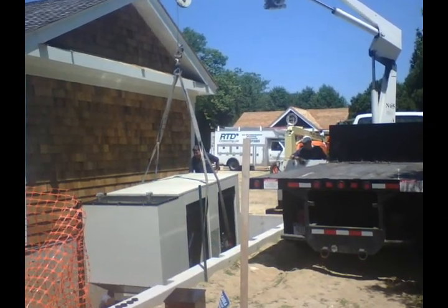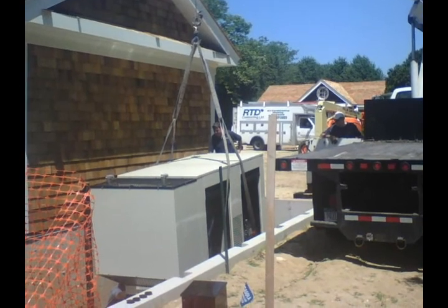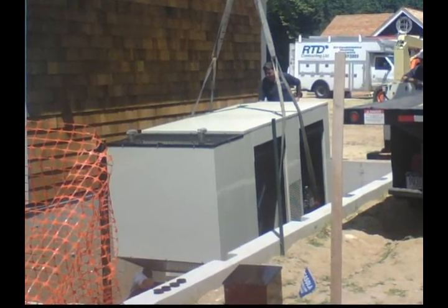Okay, see this? This is a pit. I want to talk about that a second. Hamptons, pits. Everything's in the pit in the Hamptons. If you could put the house in the pit, they would put the house in the pit. They want to see grass and trees and the geese that go all over the lawn. Pits. Big problem for generators. Why? Because the architects build them 1 foot bigger than the generator. What are you supposed to do with that?